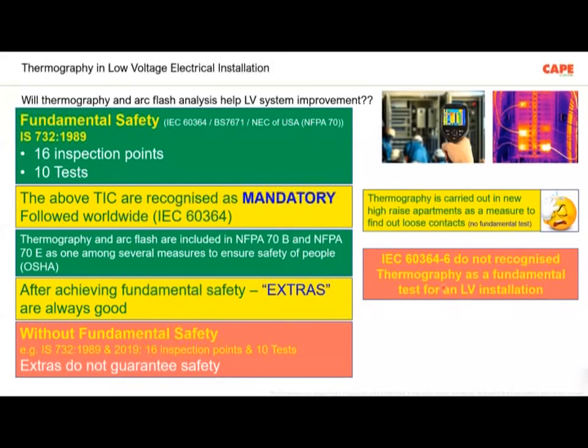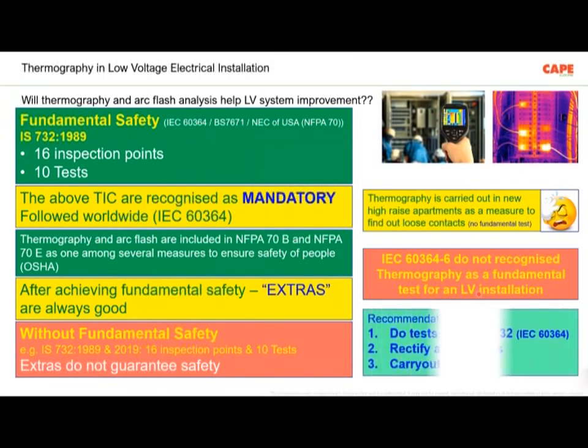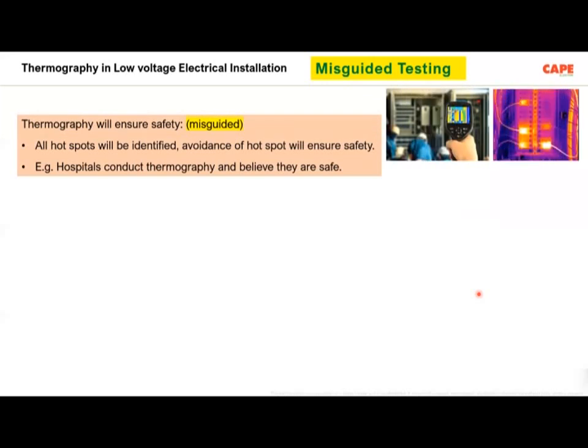So as a result, the statement which I made last time is that IEC 60364 or our Indian standard, the IS732, do not recognize thermography as a fundamental test in an LV, low voltage electrical installation. So inside a building, inside an electrical installation, thermography is not recognized as a fundamental safety requirement. If you have fulfilled the fundamental requirement, you can do it extra. So what I would recommend is you first do the test as per the IS732, rectify all the mistakes, then you carry out your extra tests, such as your thermography or arc flash study or whatever. But fundamental is there. Without fundamental, if we do only the advanced things, of course, it won't work out.